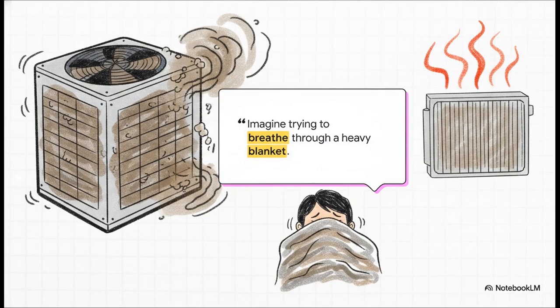Okay, let's move outside to culprit number 2, the condenser coil. This component acts like the radiator of the whole system, rejecting the heat it absorbed from the building out into the atmosphere. But when it gets caked in layers of dirt, dust, pollen, and grease, it truly struggles. As our source material perfectly puts it, imagine trying to breathe through a heavy blanket while running a marathon. That is essentially what your condenser fan is attempting to do when it gets clogged up.